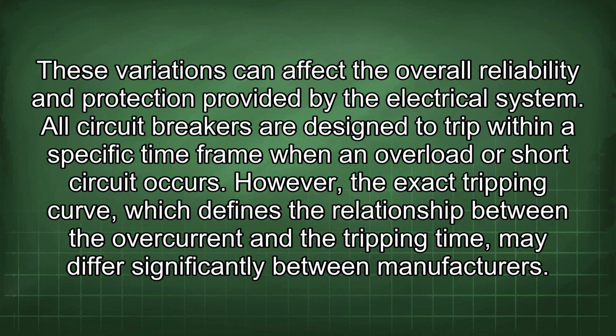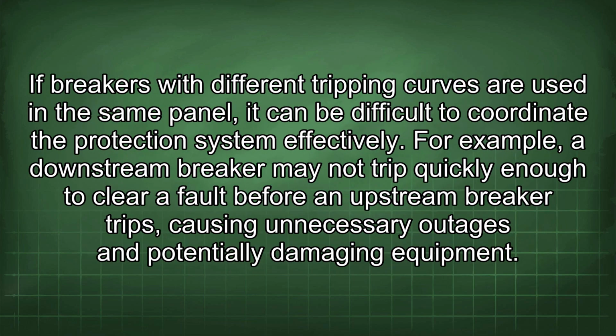All circuit breakers are designed to trip within a specific time frame when an overload or short circuit occurs. However, the exact tripping curve, which defines the relationship between the overcurrent and the tripping time, may differ significantly between manufacturers. If breakers with different tripping curves are used in the same panel, it can be difficult to coordinate the protection system effectively. For example, a downstream breaker may not trip quickly enough to clear a fault before an upstream breaker trips, causing unnecessary outages and potentially damaging equipment.